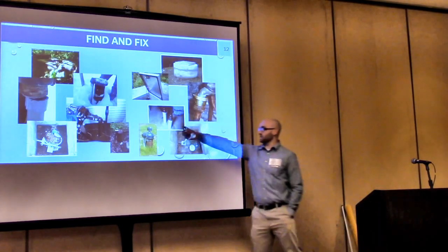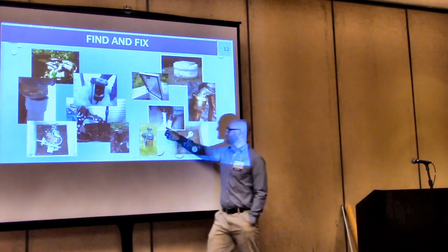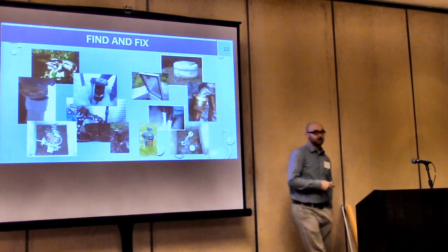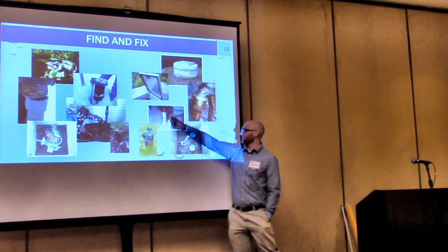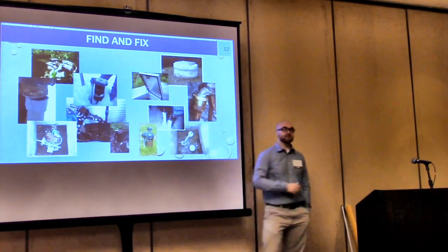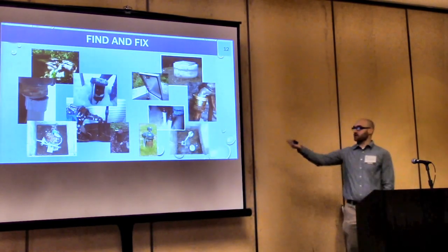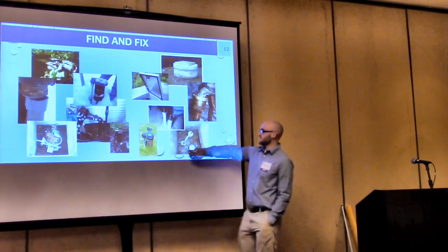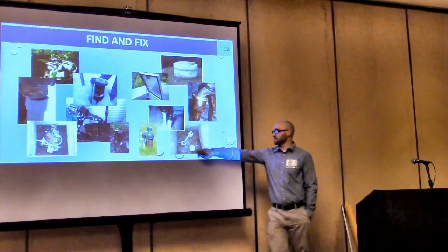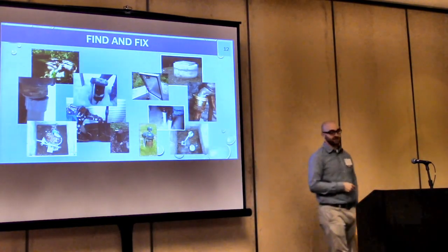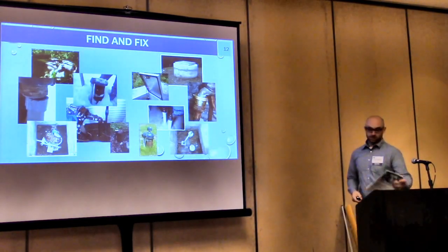So this is the same system, this one to this one. You can see a permanent sanitary conduit for which you can then have these little ferncos, whatever they're called there, so they can pull the pumps and things like that. That's what we want to see. We want to see it moving this way. This is the same tank as this one, where the operators did a great job putting in a watertight conduit, sealing the extra penetrations, making sure everything's watertight, and keeping the creepy crawlies out.